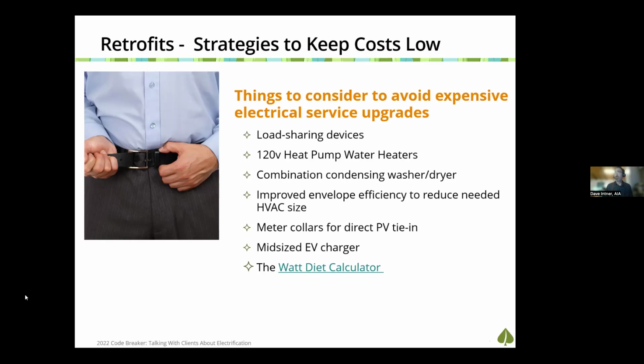A heat pump condensing washer and dryer can operate on a 120 volt outlet and wouldn't necessarily require a new circuit. Improving your envelope efficiency can help reduce your needed HVAC size, which can reduce the size you need for your compressor, which can reduce the need for potential upgrades.